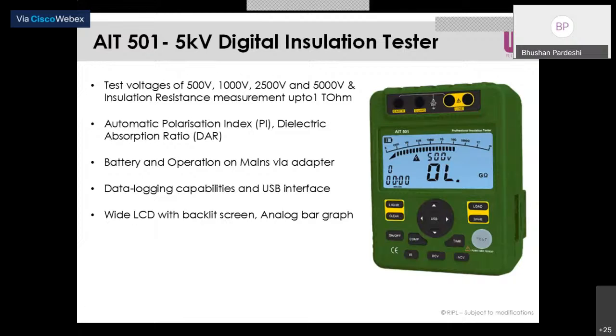Now, instantaneously, one cannot judge the insulation of any device, because many times the molecules inside the material will take some time to sustain this particular amount of voltage and resist the flow of current. So what the polarization index does is measure the time required for the molecules to resist the flow of current. It will measure the 1-minute insulation resistance value and the 10-minute insulation resistance value, and then take the ratio of the 10-minute value upon the 1-minute value.